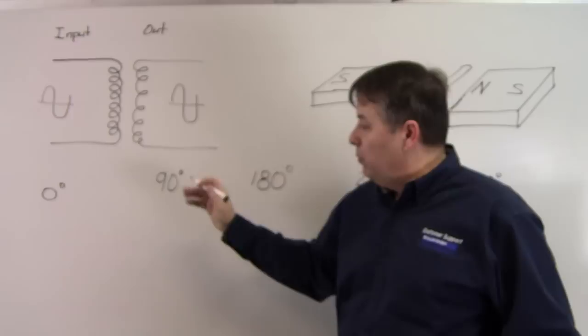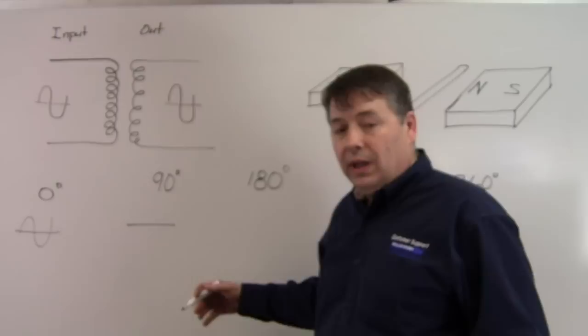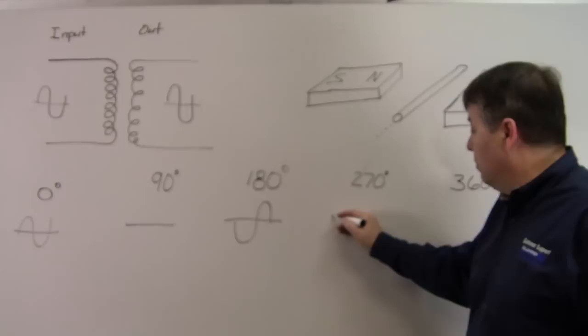So if we take our secondary and we begin rotating it, starting at 0 degrees all the way back to 360 degrees, we'll see that our signal, as we begin rotating it, is going to drop and at 90 degrees we'll be at 0. As we continue rotating from 90 degrees to 180, we're going to see our signal come back, but we'll notice that it's out of phase.